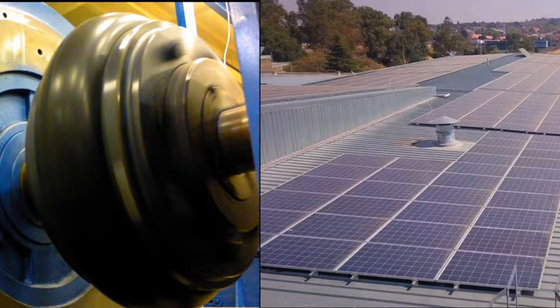The one thing that's come about lately is synthetic inertia, and it's become a bit of a buzzword, because typically as we introduce these new sources of energy, we're reducing the amount of inertia-based generation, so rotating generation, that exists. There are certain benefits that come with that rotating generation that we're now seeing, that as we start removing it or replacing it with electronic inverter-based generation, we're running into a few issues.